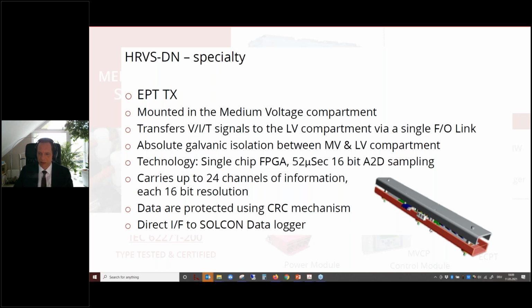And one nice thing about this is with this device, you can kind of cheat the soft starter and make it believe it sees 6 kV voltage, where in fact only 400 volt is connected. And you can do a full low voltage test and a full parameterization of the soft starter while utilizing low voltage. And this is really time saving when talking about commissioning of a soft starter, because you need specially trained people to work on the medium voltage, and switching the medium voltage on and off takes time. Doing this in advance with the low voltage is a big advantage here.